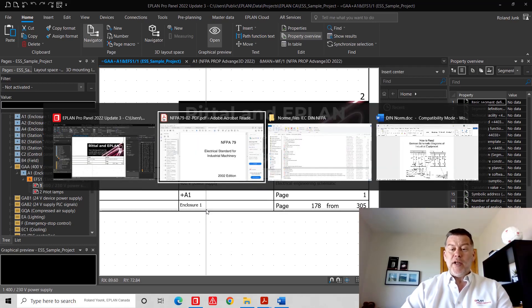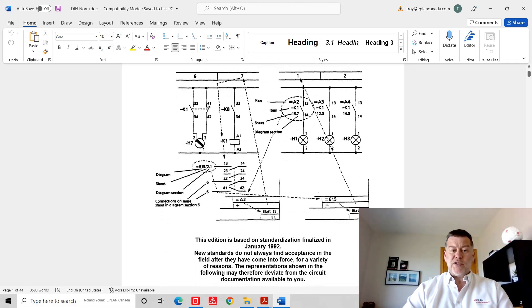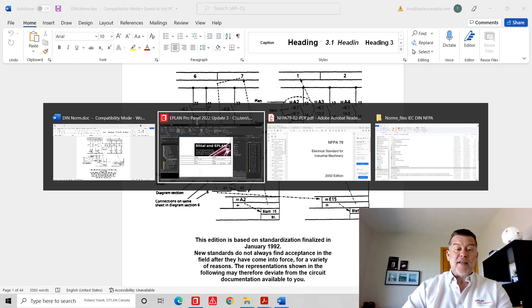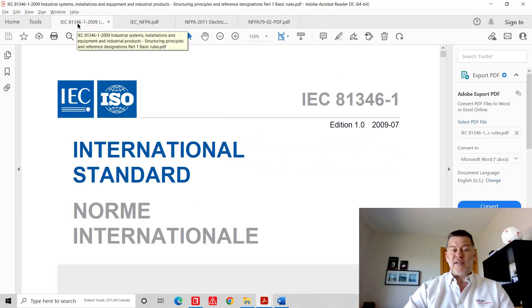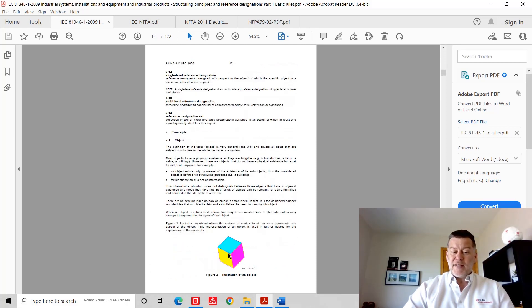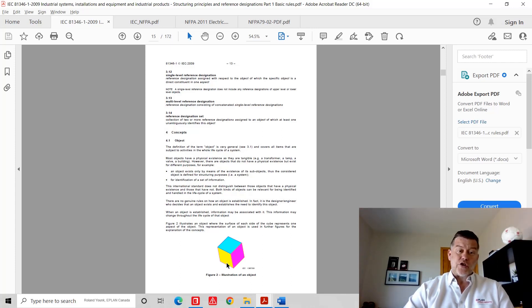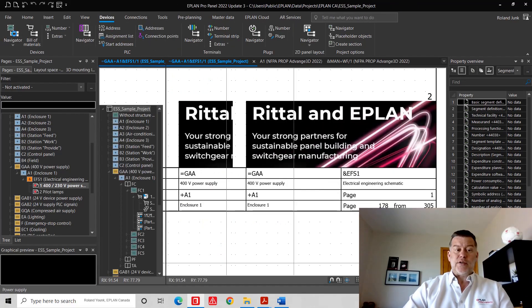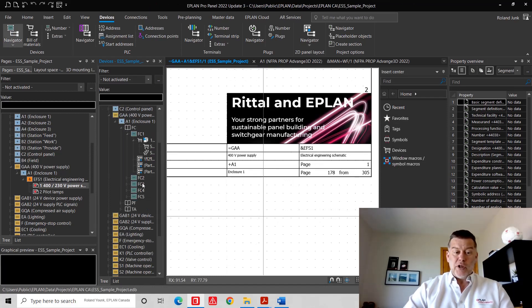These structural elements come from how you read schematics — you always look at the bottom of the page, where you can see the equal function, plus location, and a page number. This reflects the total designation of the components. This information can also be found in IEC documents, where scrolling down you find this specific cube which refers to a functional aspect, a location aspect, and the device component itself. This structure lets you look for a specific function or location and quickly find what the component does and where it is.